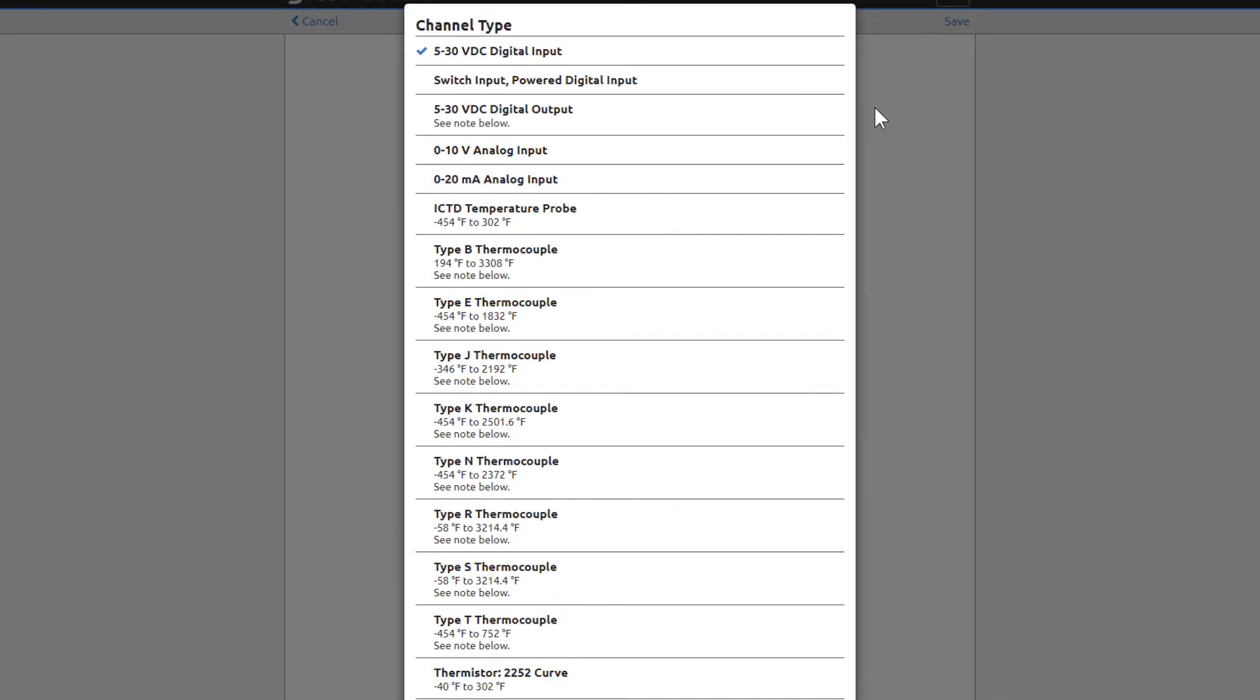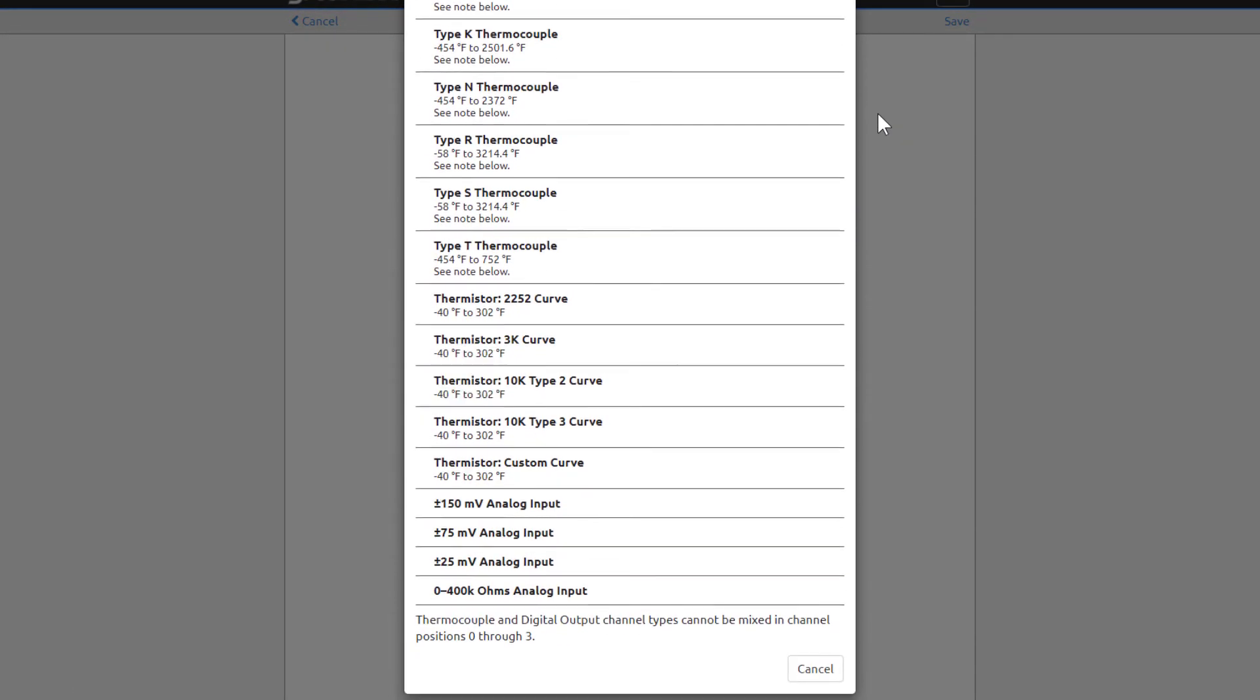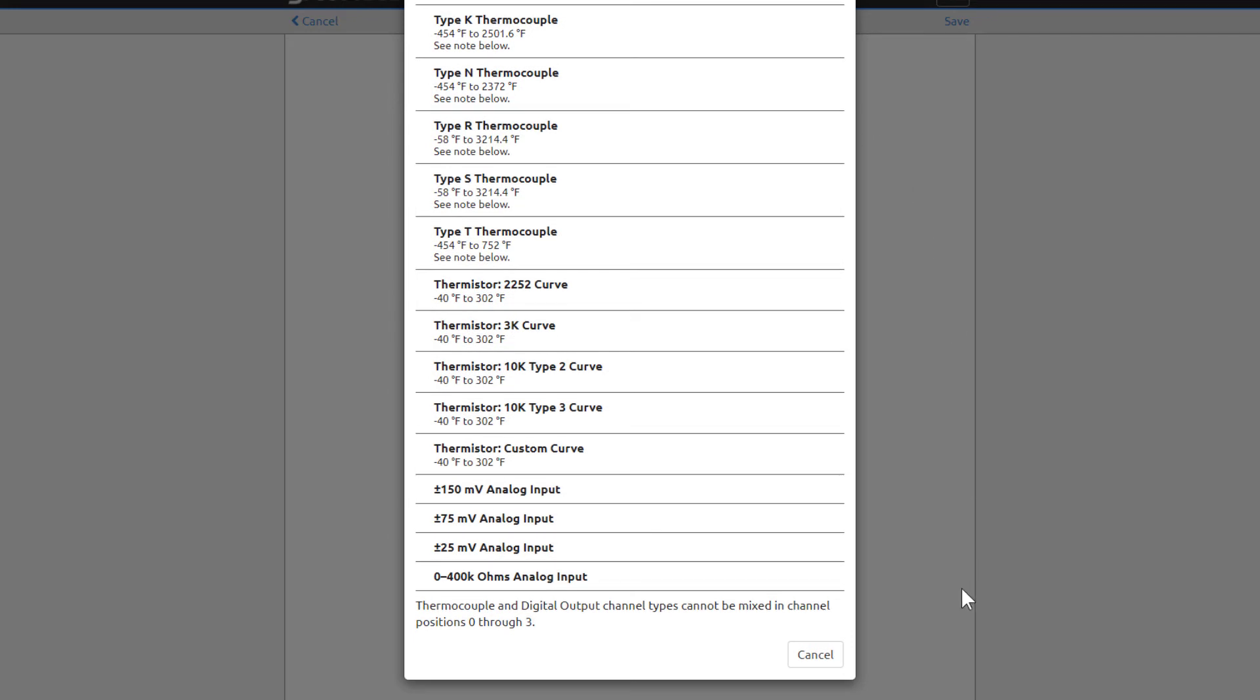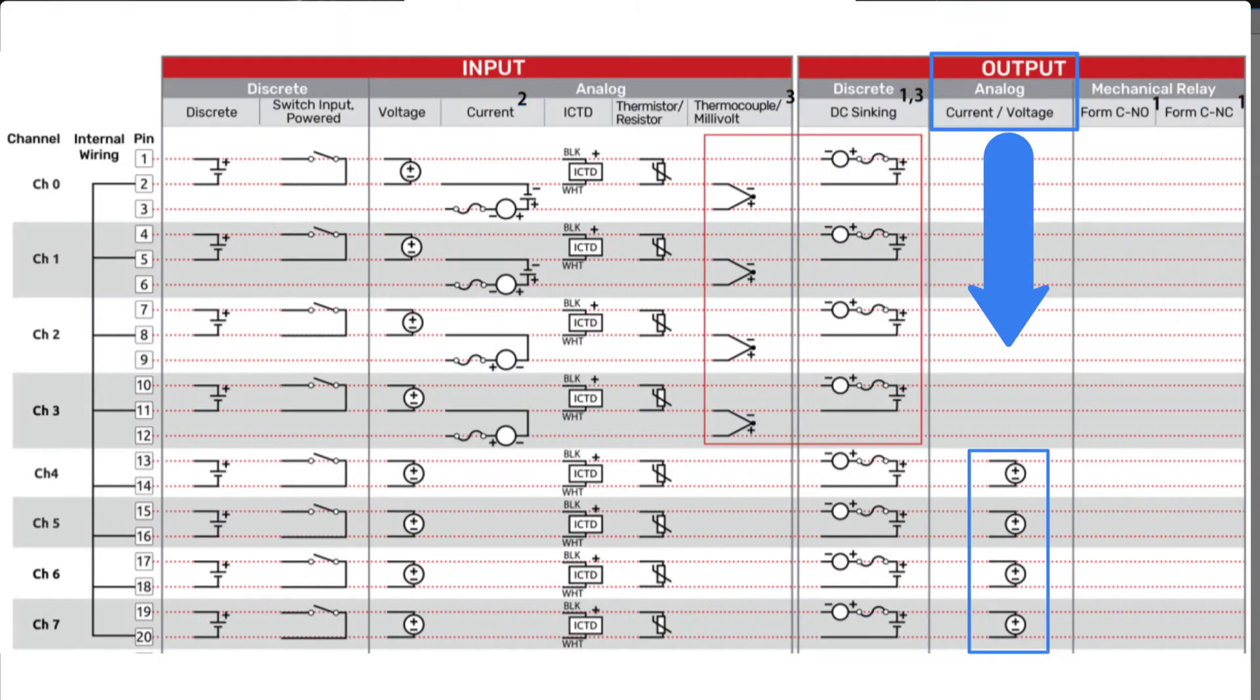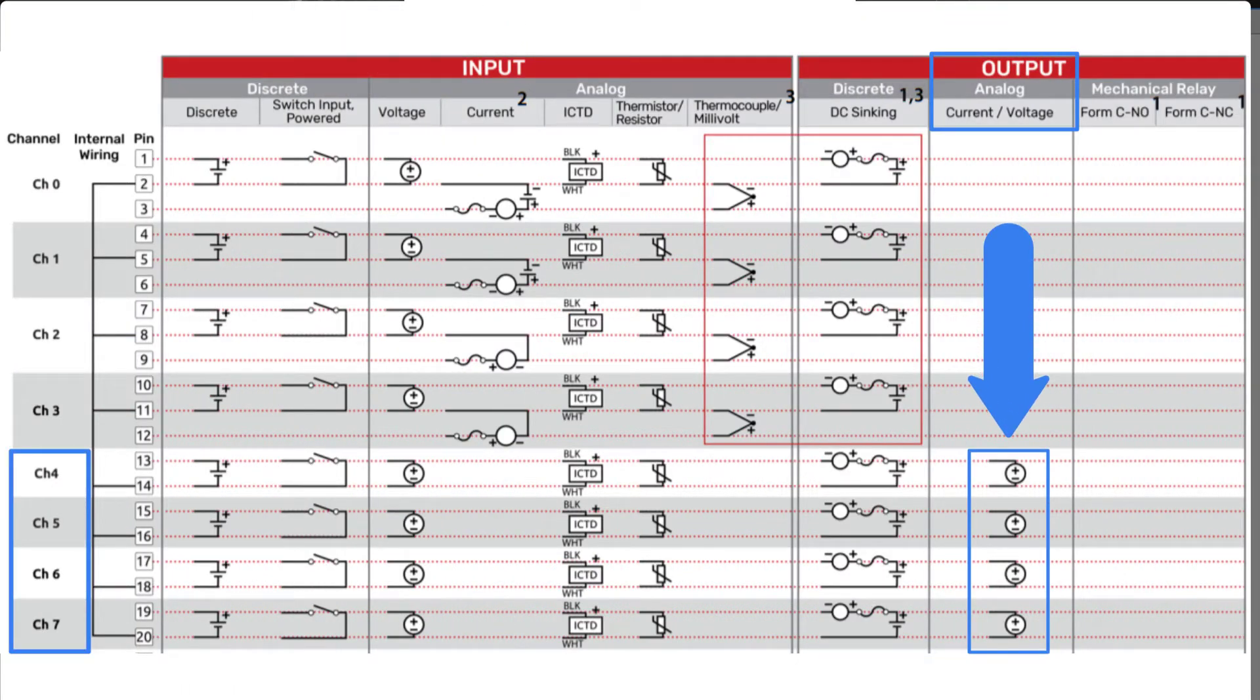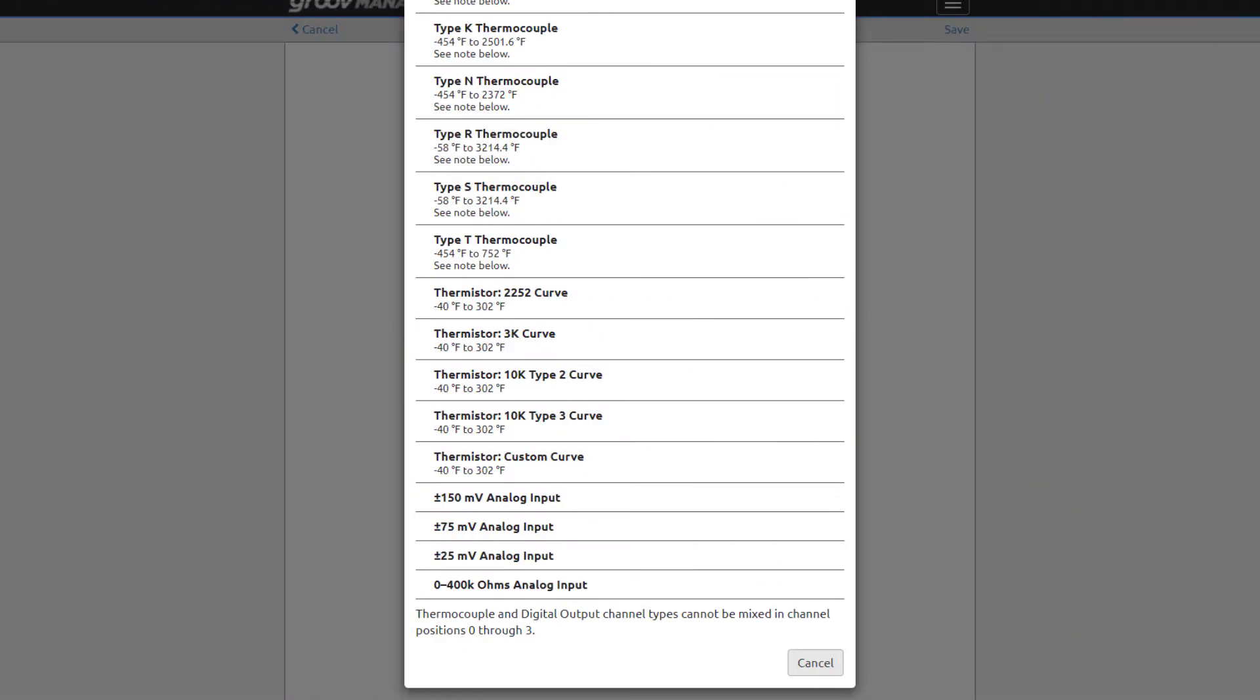The options for this channel are all listed here: digital input, analog voltage and current input, thermocouple, thermistor, and resistive input. For example, notice analog output channels are not on this list. That's because they're only allowed on channels 4 through 7. Click cancel.